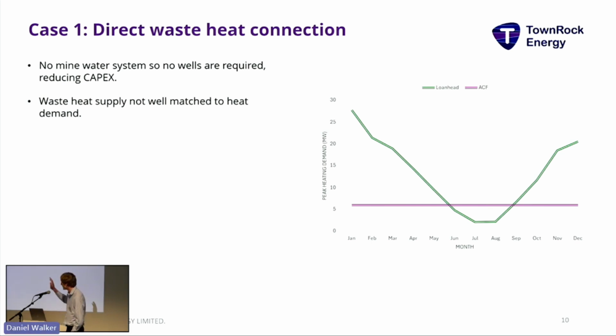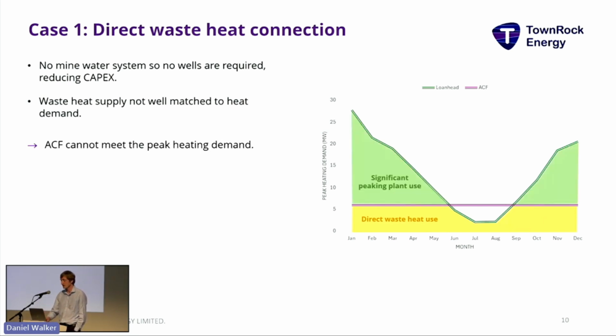As you can see in this graph in purple, the waste heat supply is 6 megawatts throughout the year, but the demand of our proposed Loanhead network actually varies quite a lot throughout the year, as you'd expect, with seasonal demand variation. So it's not that well matched to the heat demand. The idea is that where you can, you use the direct waste heat from the data center.